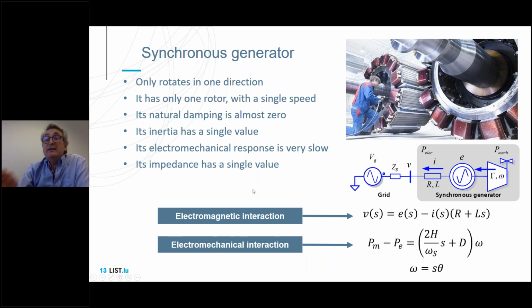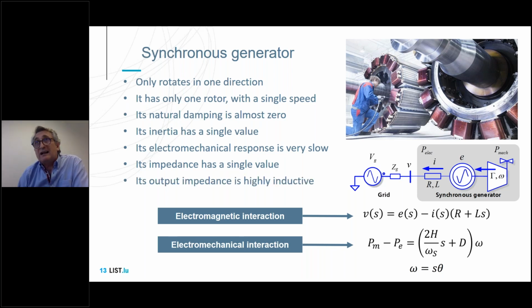The impedance has a given value. Of course, we are talking about maybe transient impedance and synchronous impedance, but at the end of the day, they have a given value. We don't have a given impedance for the seventh harmonic, another one for the fifth harmonic, another one for the negative sequence. These impedances are highly inductive in a synchronous generator, purely inductive, which gives rise to interactions with capacitance and other elements in the grid during transients.